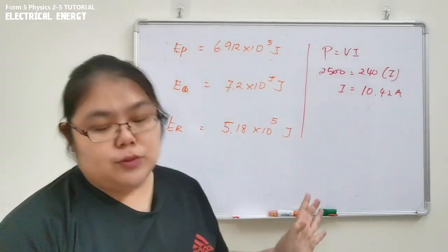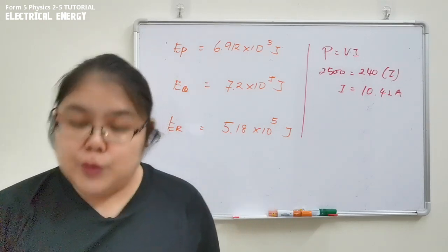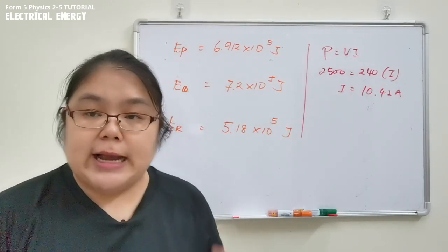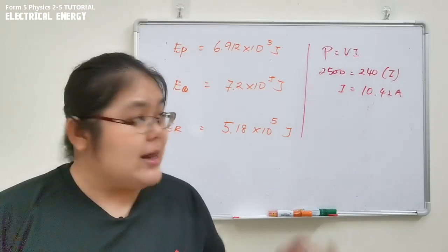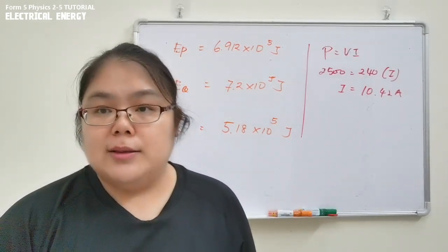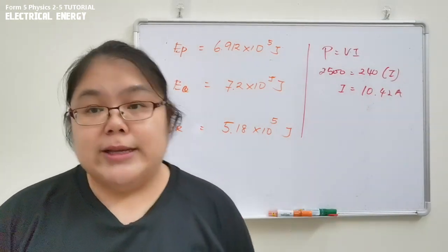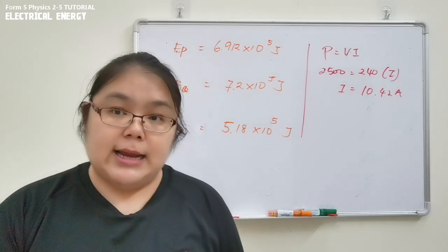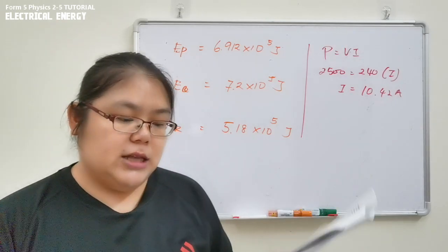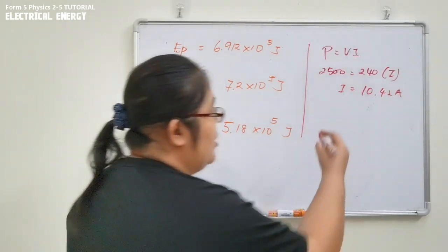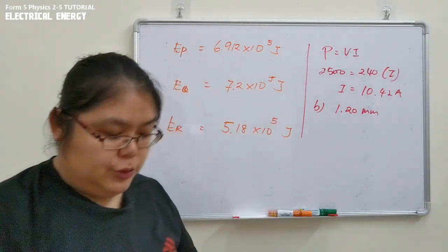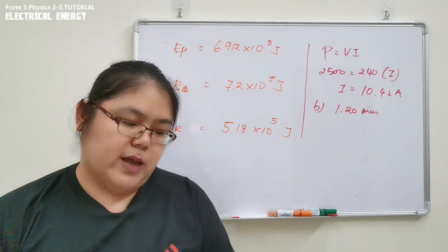Since our current is 10.42 A, we cannot choose the 1 mm wire rated at 10 A because that would be exceeded. We choose the next size up — 1.20 mm — which supports 13 A, slightly greater than the required current. So the answer is 1.20 mm diameter wire.